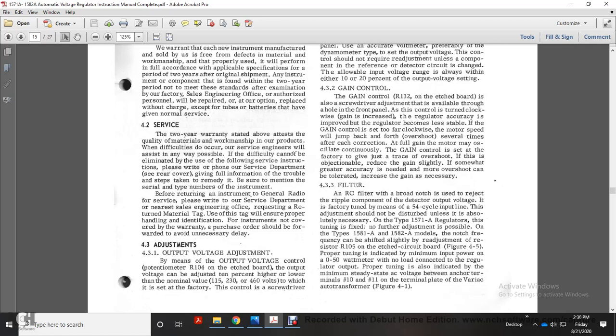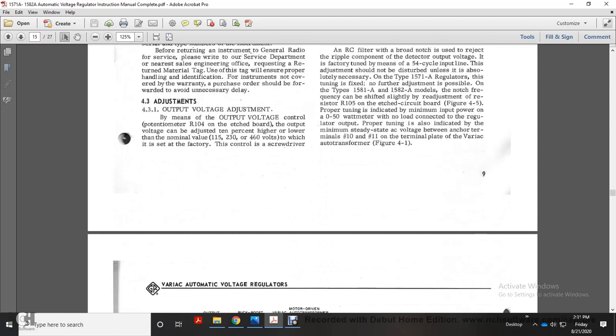4.3.3 The filter. The RC filter with the broad notch is used to reject the ripple component of the detector output voltage. It is tuned at the factory to the 54-cycle input line, and the adjustment should not be disturbed unless absolutely necessary. In the type 1571A regulators, the tuning is fixed and no further adjustment is possible. In the type 1581 and 1582A models, the notching frequency can be shifted slightly with readjustment of the resistor R105 on the etched circuit board, figure 4.5. Proper tuning is indicated by the minimum input power on a 0 to 50 watt meter with no load connected to the regulator output. Proper tuning is also indicated by the minimum steady state voltage between the anchor terminals number 10 and 11 on the terminal plate of the Variac autotransformer, figure 4.1.